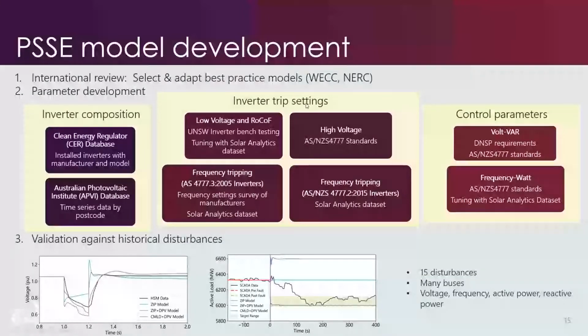Then looking at what the inverter trip settings might be - tripping on things like voltage, rate of change of frequency, high voltage, and frequency, based on various different sources for older and newer inverters. And then looking at the control parameters as well, because there's controlled behaviours we need to capture, things like volt-var response, frequency-watt response, and so on, defined under various standards and DNSP requirements.